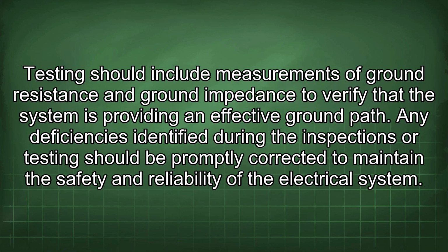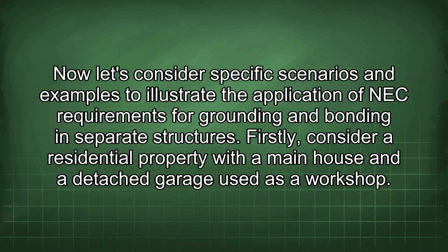Testing should include measurements of ground resistance and ground impedance to verify that the system is providing an effective ground path. Any deficiencies identified during the inspections or testing should be promptly corrected to maintain the safety and reliability of the electrical system.